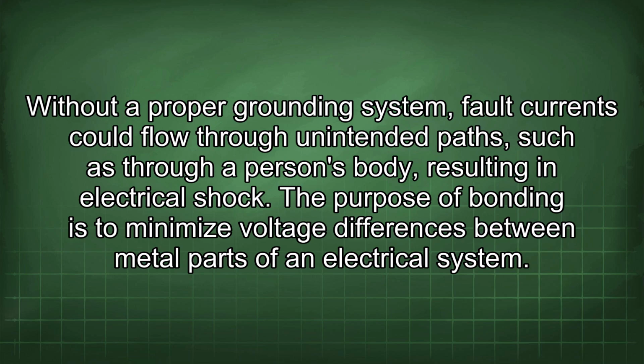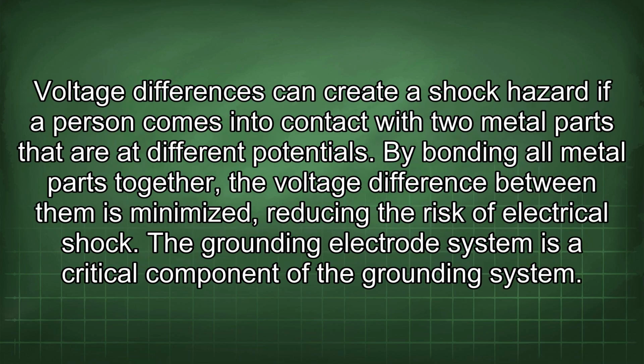The purpose of bonding is to minimize voltage differences between metal parts of an electrical system. Voltage differences can create a shock hazard if a person comes into contact with two metal parts that are at different potentials. By bonding all metal parts together, the voltage difference between them is minimized, reducing the risk of electrical shock.